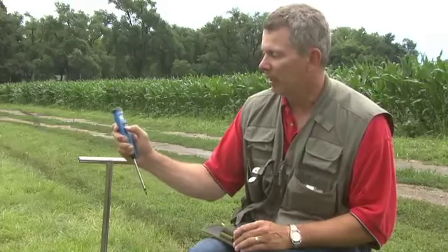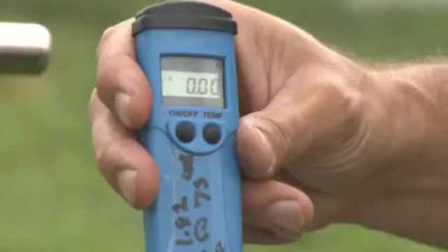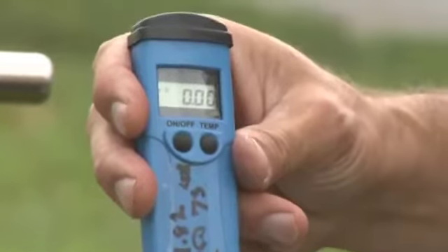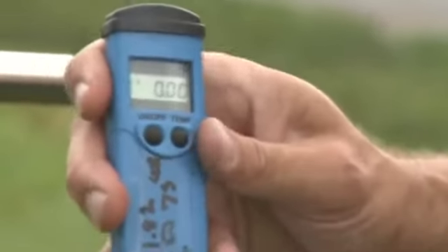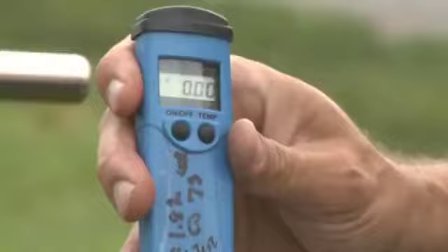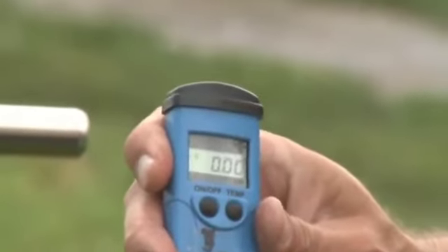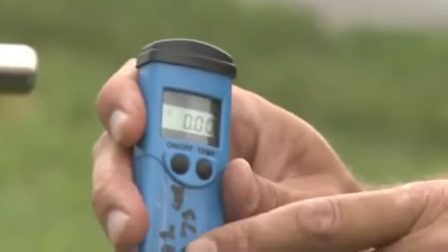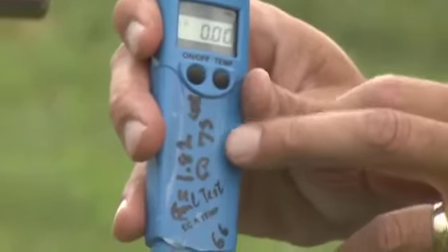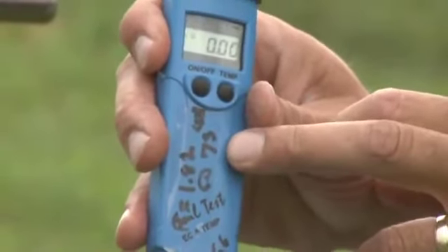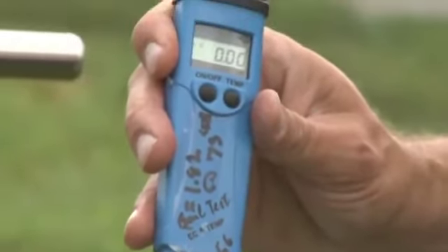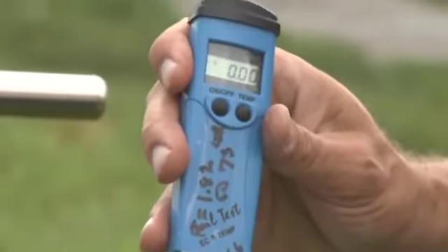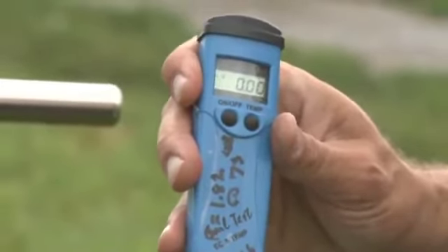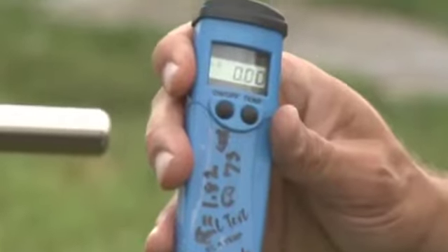And then we simply turn it on, press the on button like that, and it should read as 0. Okay. And on the front of the probe, you'll see that it's got an R value, which is a resistivity measure of 1.82 at 73 degrees Fahrenheit. And that was done to test when we calibrated with the calibration solution. And so you do not have to do that every time.